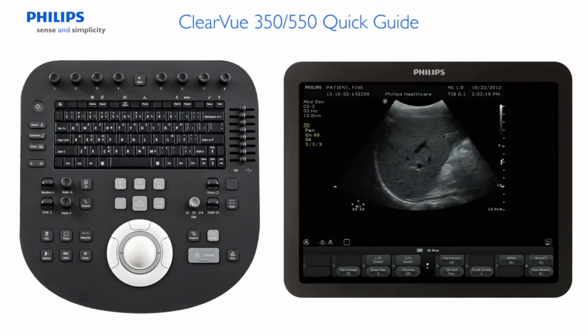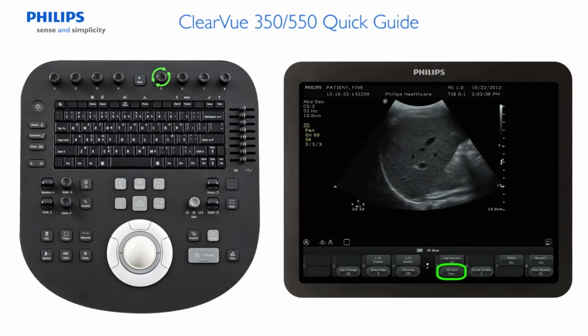The next section will discuss the system controls used to optimize the 2D imaging. The 2D Opt Quick Key settings will control the transmit and receive frequencies for the transducer. Each 2D Opt setting is optimized for one or more of the following: penetration, general, and resolution. 2D Opt settings apply to 2D mode and tissue harmonic imaging. Turn the 2D Opt Quick Key to vary the 2D optimization setting.